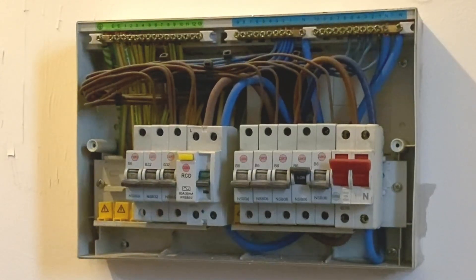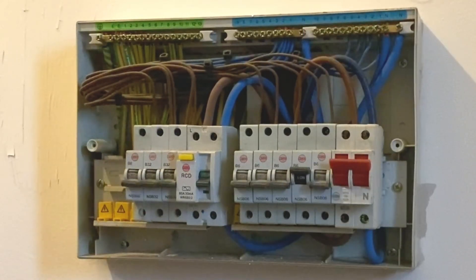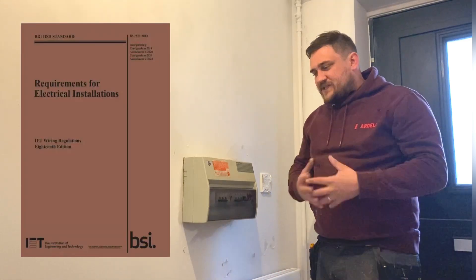It's always important to remember that BS 7671 is the minimum requirement. As part of this EICR I will still go and test it at times five. The amendment hasn't been around long, so it will take a while for people to get used to different methods. I'll still probably test at times one, times five, times half, and then use the test button to make sure it's effective.